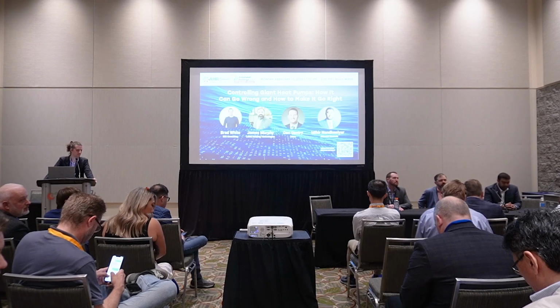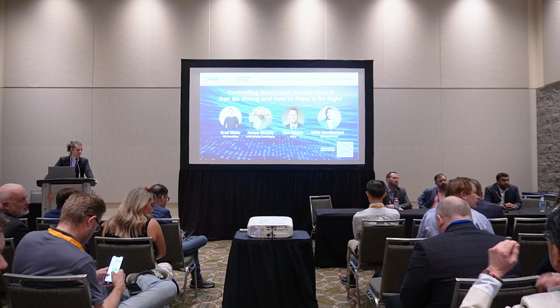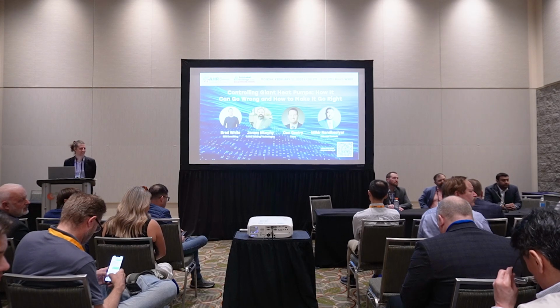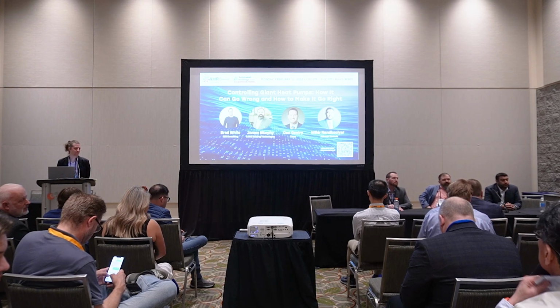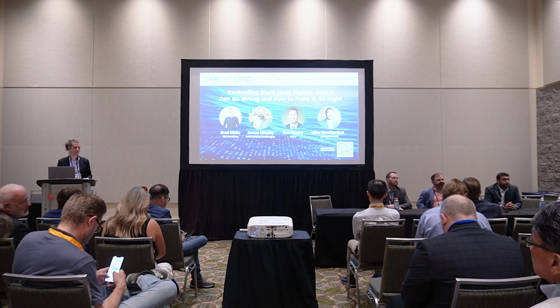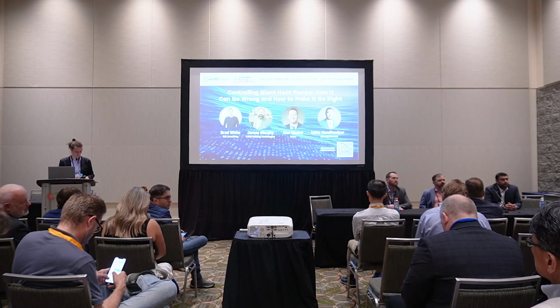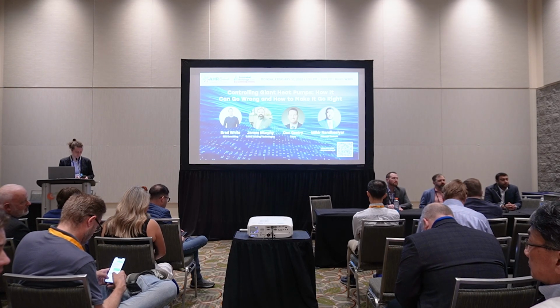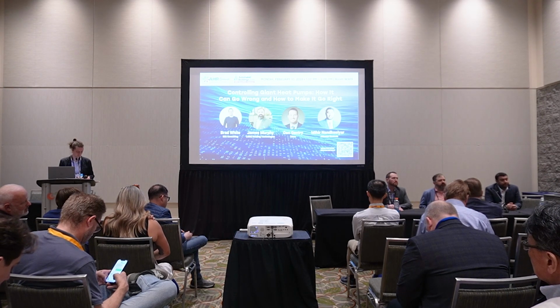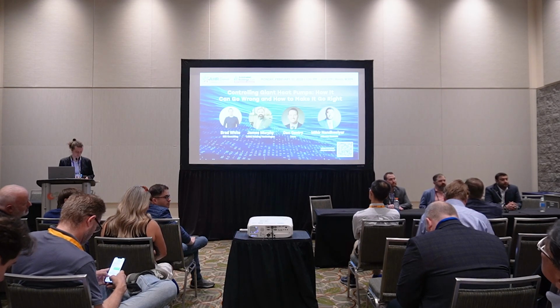I am, however, leading or co-leading the effort under ASHRAE Guideline 36 to include heat pumps in Guideline 36. Almost every one of the issues you brought up are issues that our committee members are bringing up as well. The lack of documentation and the lack of understanding of how your internal controls work are an incredible frustration across the board, and we need to figure out how to work better on that. We've brought half a dozen manufacturers onto our committee to help with this issue, but it is a challenge, because you can describe how yours works and the designer can design around it, and then if the contractor selects a different product, you're back to square one.